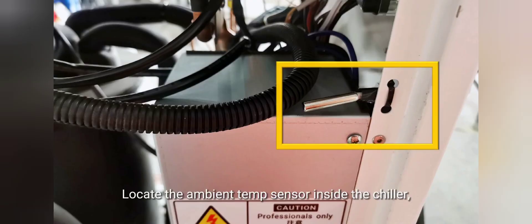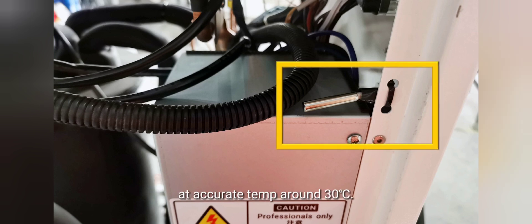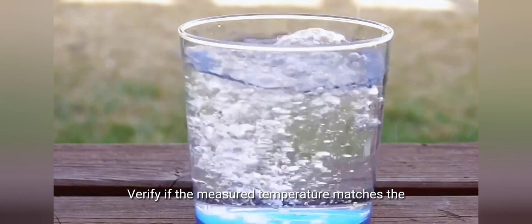Locate the ambient temp sensor inside the chiller. Then perform constant temperature testing by placing the sensor in water at accurate temp around 30 degrees Celsius, verifying if the measured temperature matches the actual value.